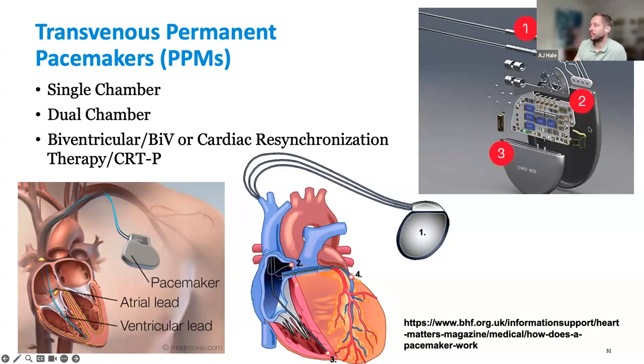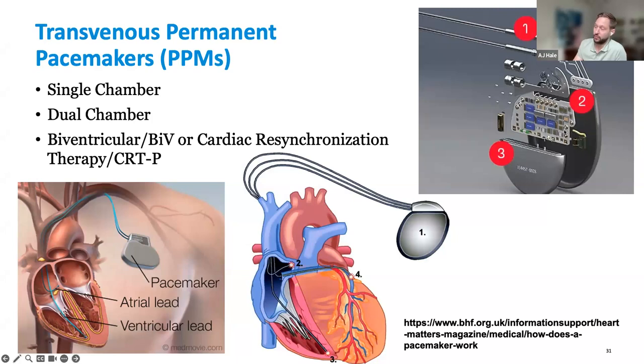As for the device makeup for your pacemakers, it's actually much more complex, but simplified: you have your device header where the leads plug in — usually polyurethane and transparent. Then you have your circuit board, which is the brain of the device, fully encapsulated so there's no ingress of fluid. And then, typically at the bottom, you have your battery, which charges and powers the whole device.